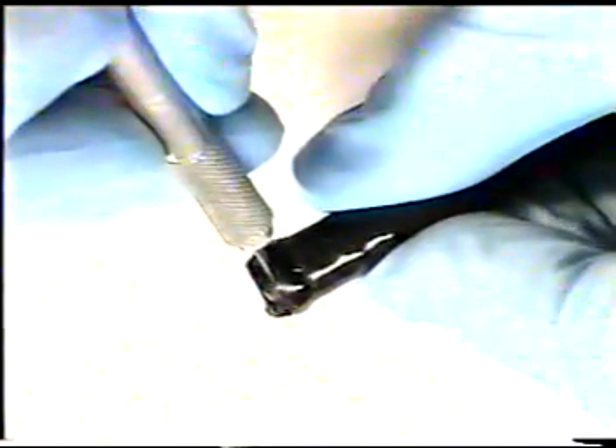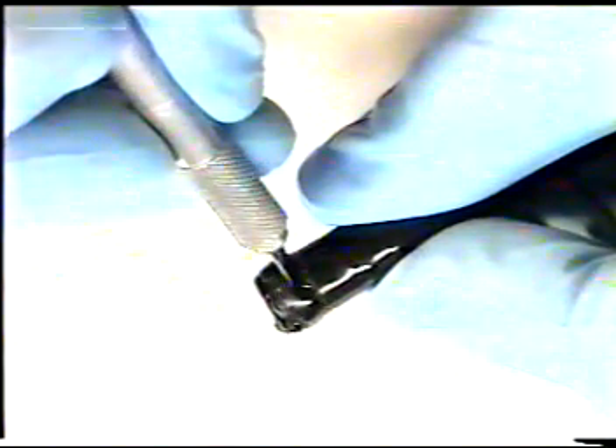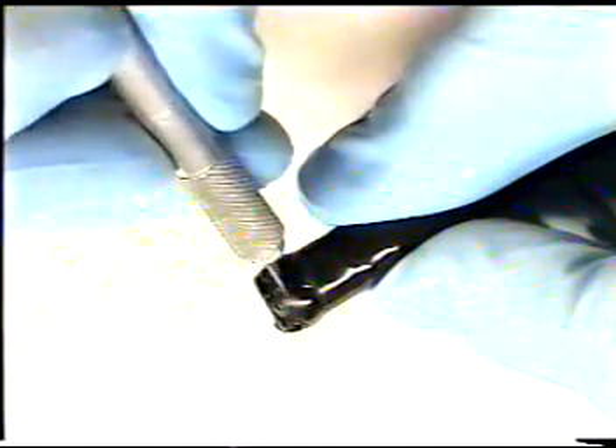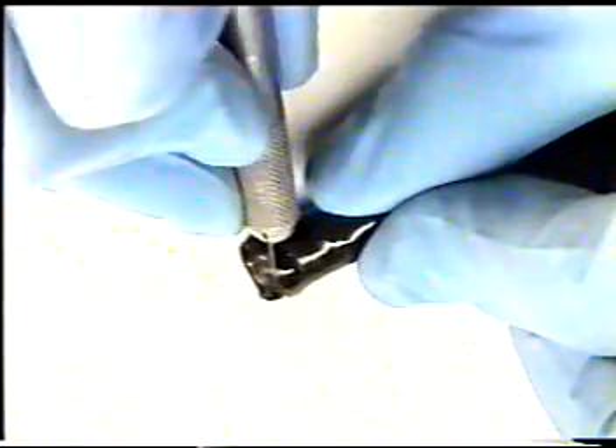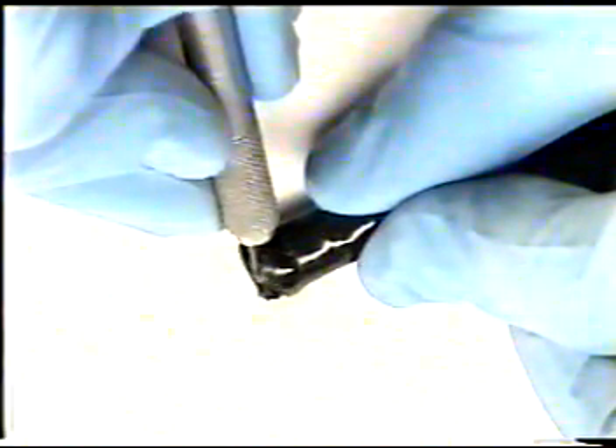As long as you have all the materials you have just seen, we can now start with the removal and replacement of the bending rubber sheath. Start at the distal end. We shall remove the bending rubber glue joint at the distal tip of the scope first. Using a sharp X-Acto knife, we cut diagonally into the glue joint, being careful not to cut into the distal end hood assembly itself.